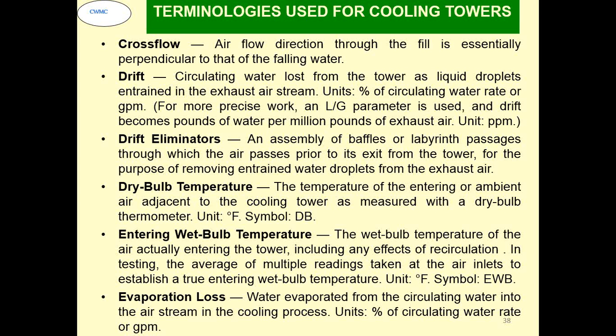Dry bulb temperature, it is the temperature of the entering or the ambient air adjacent to the cooling tower as measured with the dry bulb thermometer. Symbols are degree Fahrenheit or degree centigrade. Entering wet bulb temperature, it is the wet bulb temperature of the air actually entering the tower, including any effects of recirculation. In testing, the average of multiple readings taken at the air inlets to establish a true entering wet bulb temperature. Units are again degree Fahrenheit and centigrade.